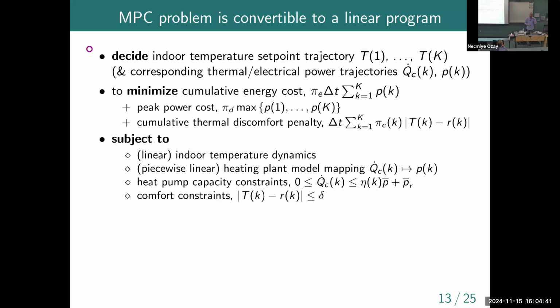The constraints are the linear thermodynamics shown earlier, plus data-driven equipment models learned from manufacturer spec sheets and data, and capacity constraints—the heat pump can only produce so much power and can't easily switch between heating and cooling, so the thermal power provided can't go negative. We also have comfort constraints: in addition to the soft tracking error penalty, there's a hard constraint on temperature deviation from the preference.